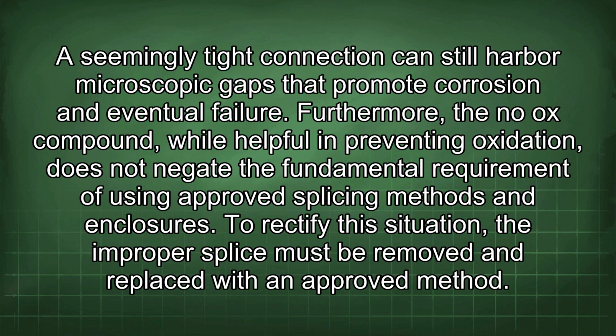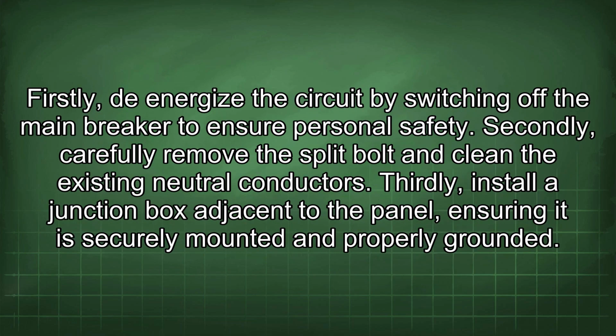A seemingly tight connection can still harbor microscopic gaps that promote corrosion and eventual failure. Furthermore, the no-ox compound, while helpful in preventing oxidation, does not negate the fundamental requirement of using approved splicing methods and enclosures. To rectify this situation, the improper splice must be removed and replaced with an approved method. Firstly, de-energize the circuit by switching off the main breaker to ensure personal safety. Secondly, carefully remove the split bolt and clean the existing neutral conductors.